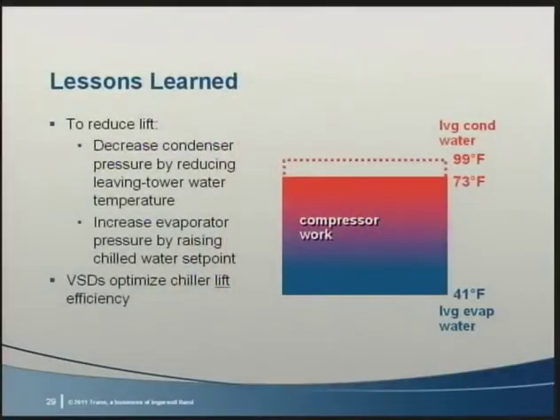Mass flow, or tons, is defined by the building. For a given mass flow, the speed of the compressor can only be reduced if the lift is reduced. Lift is reduced, one, by lowering the condensing temperature by delivering colder condenser water than design, and two, by increasing the evaporator temperature by resetting the chilled water set point warmer.